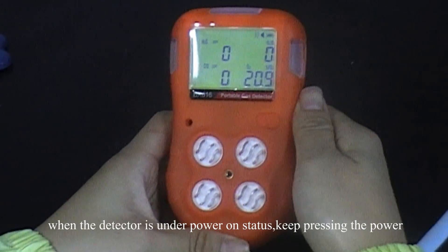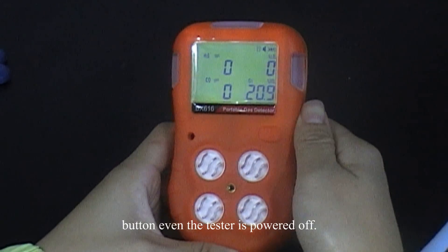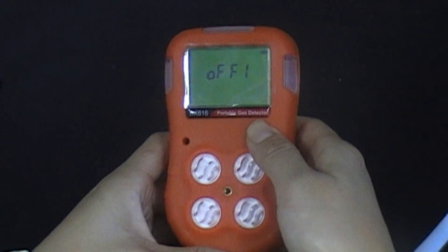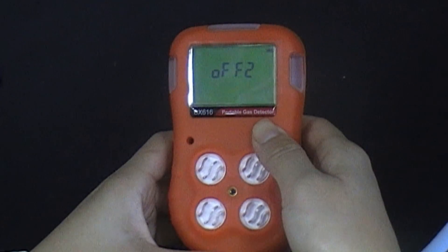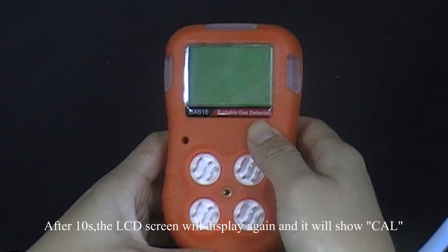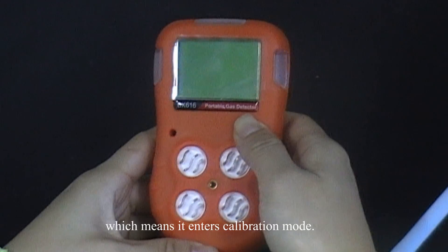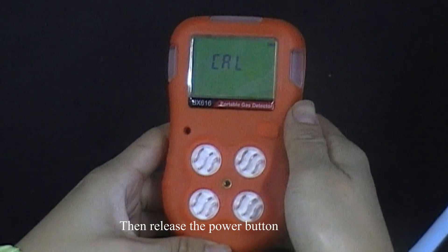When the detector is under power-on status, keep pressing the power button, even as the tester powers off. After 10 seconds, the LCD screen will display again and show 'CAL', which means it has entered calibration mode. Then release the power button.